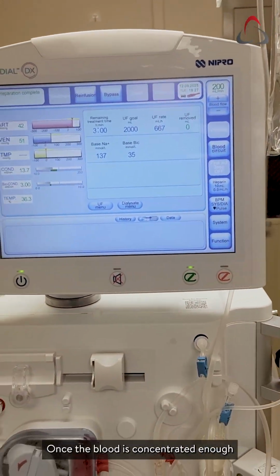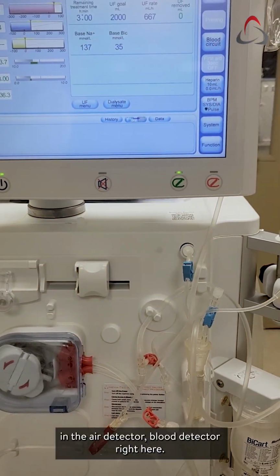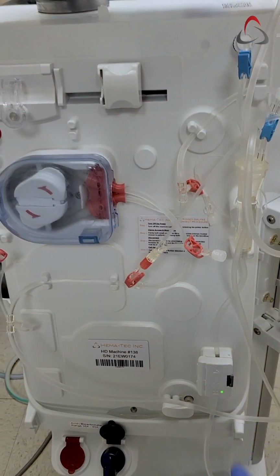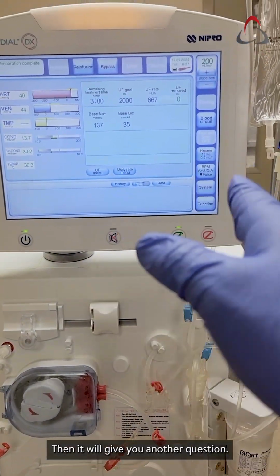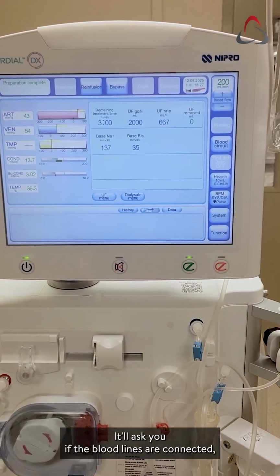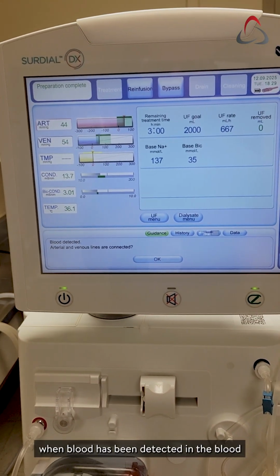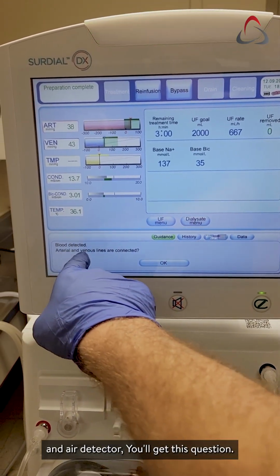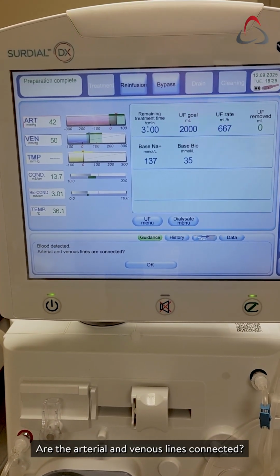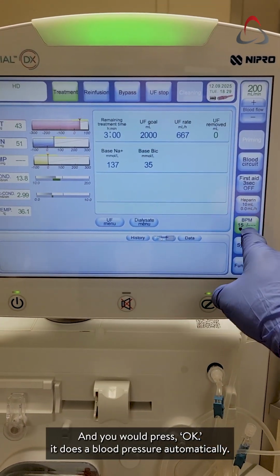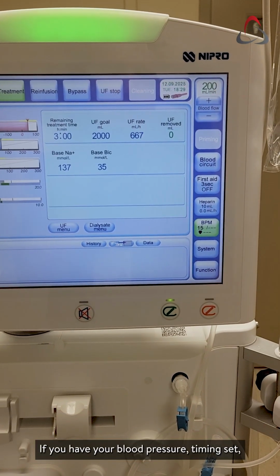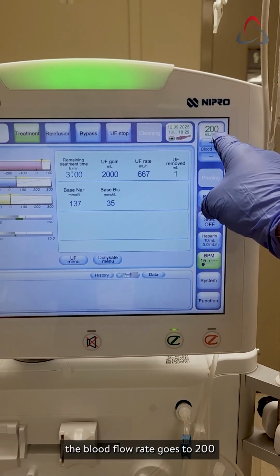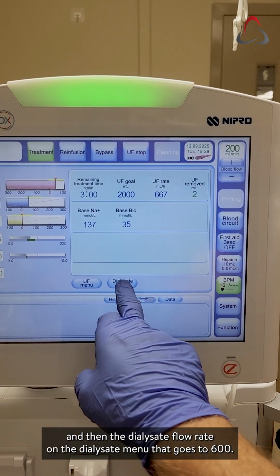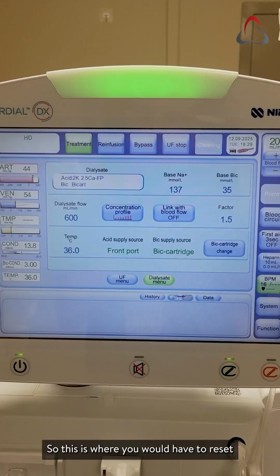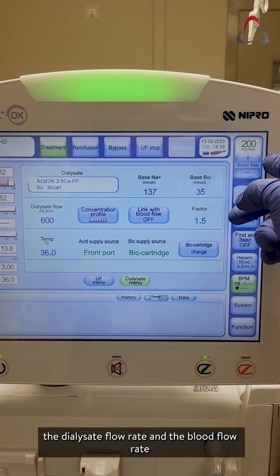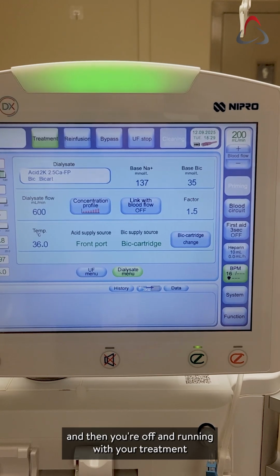Once the blood is concentrated enough in the air detector blood detector right here, then it will give you another question. It'll ask you if the blood lines are connected. When blood has been detected in the blood and air detector, you'll get this question, are the arterial and venous lines connected? And you would press OK. It does a blood pressure automatically if you have your blood pressure timing set. The blood flow rate goes to 200, and then the dialysate flow rate on the dialysate menu, that goes to 600. So this is where you would have to reset the dialysate flow rate and the blood flow rate. And then you're off and running with your treatment.